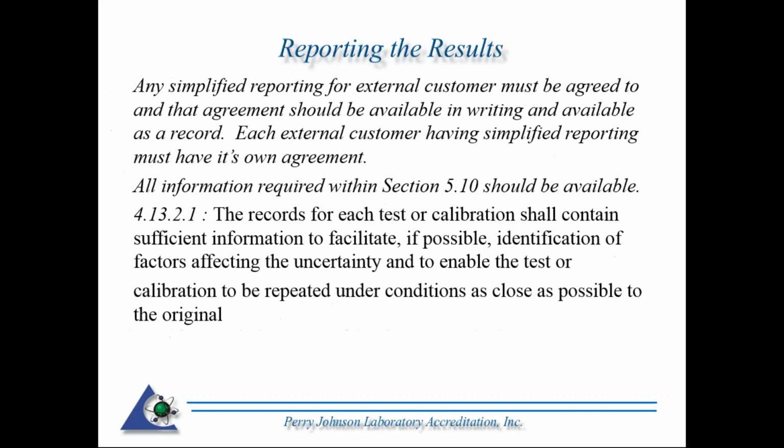I'm going to talk about simplified reporting for external customers. If you're a testing or calibration lab, these are your customers from the outside sending you samples, artifacts to test. When can simplified reporting be done in those cases? Any simplified reporting for external customers must be agreed to, and that agreement should be available in writing and available as a record.